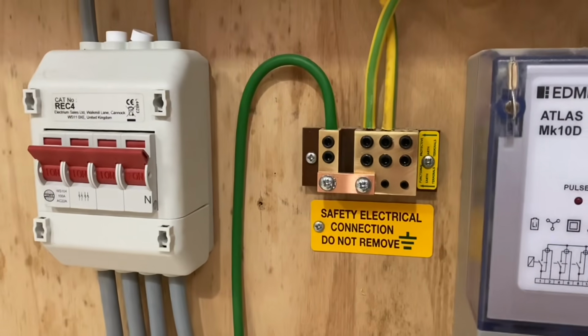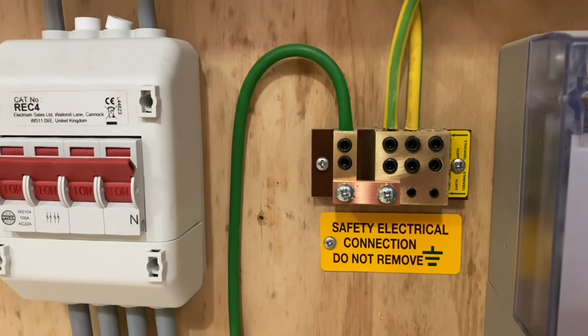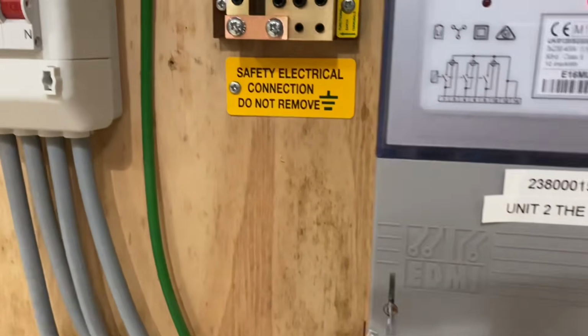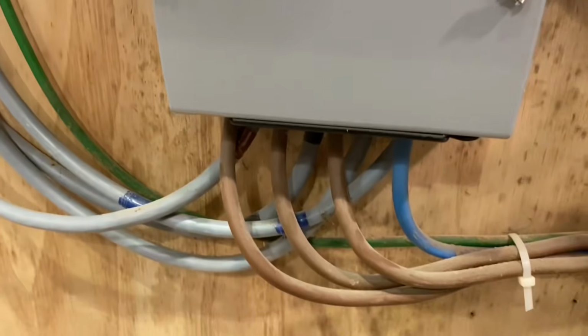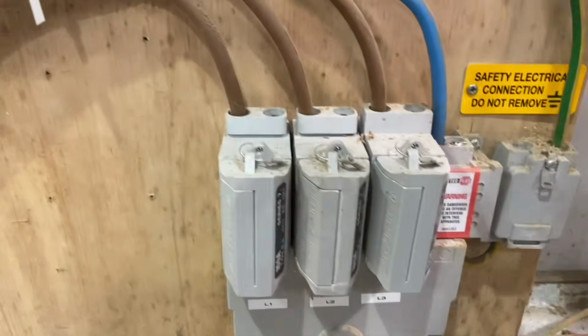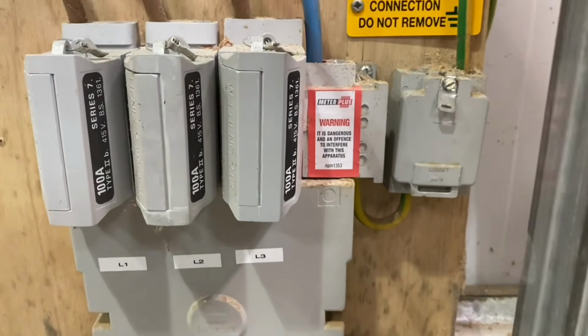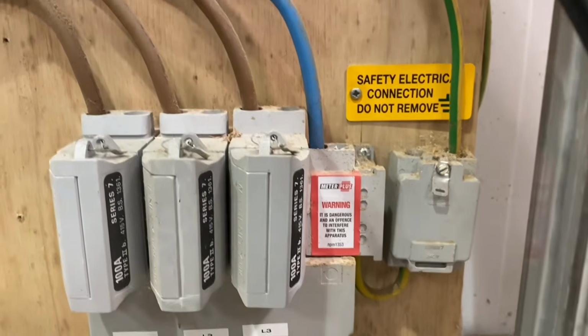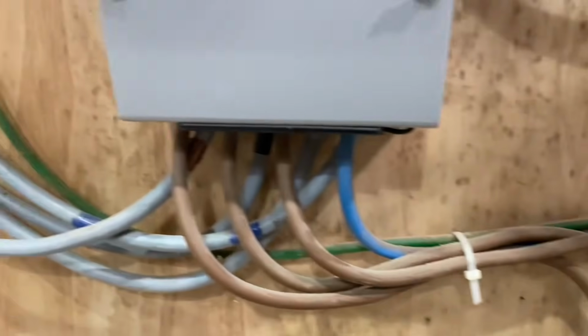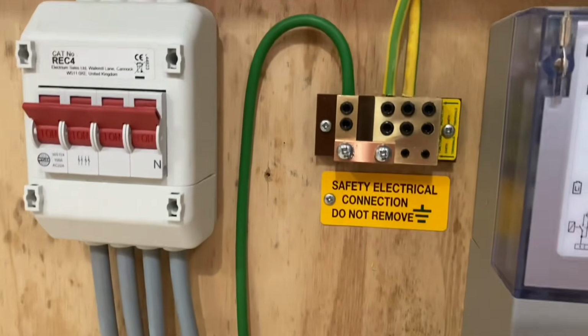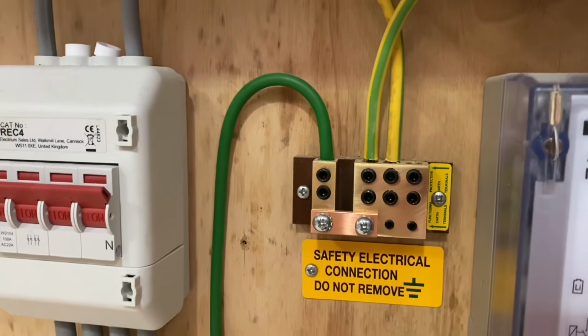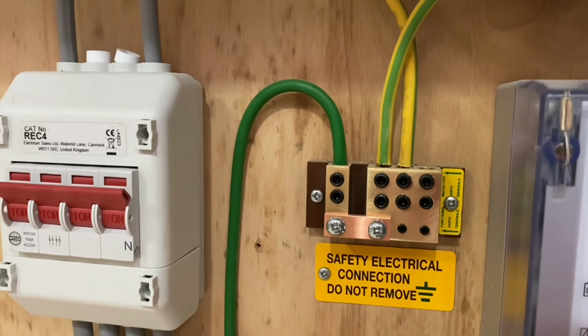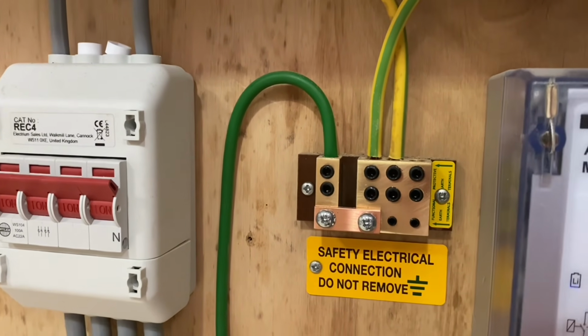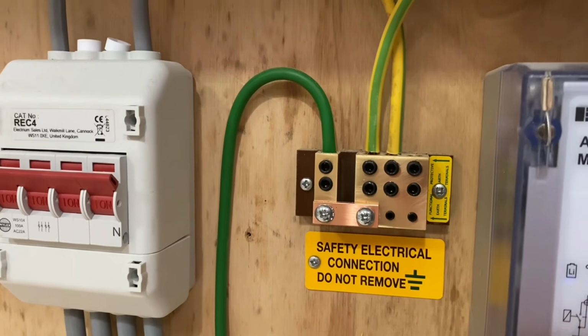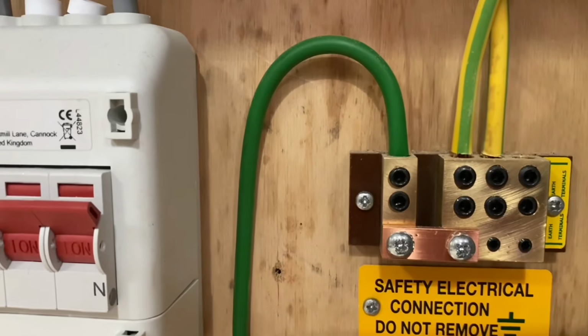This video is all about reminding you to remove parallel earth paths when testing for AM2 and AM2S. We've got a three-phase supply, we've got our three cut-out fuses, our neutral and earth are linked together. Our earthing arrangement for this system is TNCS.